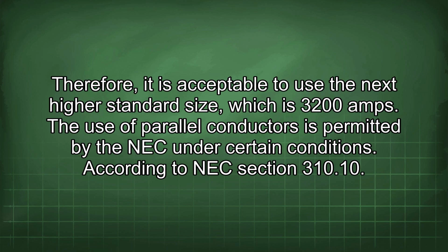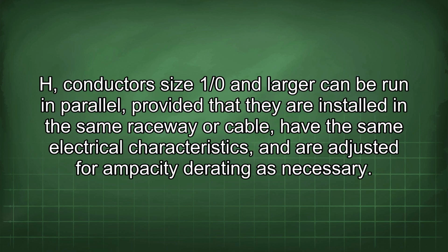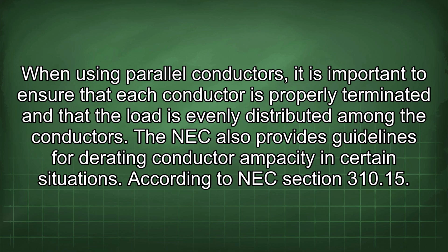The use of parallel conductors is permitted by the NEC under certain conditions. According to NEC Section 310.10(H), conductor sizes 1/0 and larger can be run in parallel, provided that they are installed in the same raceway or cable, have the same electrical characteristics, and are adjusted for ampacity derating as necessary. When using parallel conductors, it is important to ensure that each conductor is properly terminated and that the load is evenly distributed among the conductors.